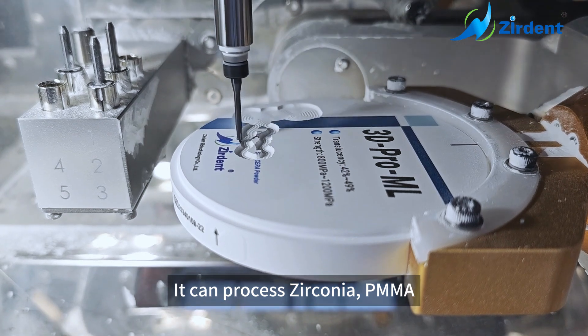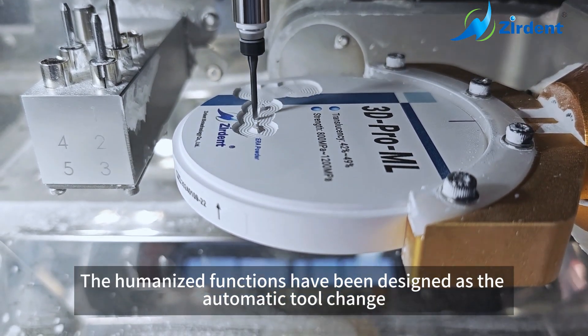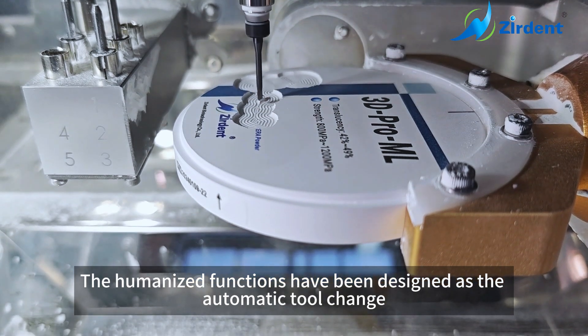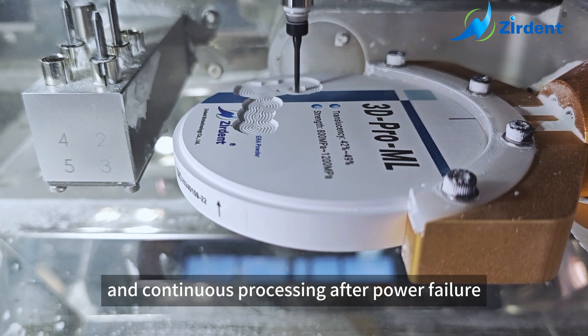It can process zirconia, PMMA, PEEK, and wax. The humanized function has been designed with automatic bur change, broken bur detection, and continuous processing after power failure.